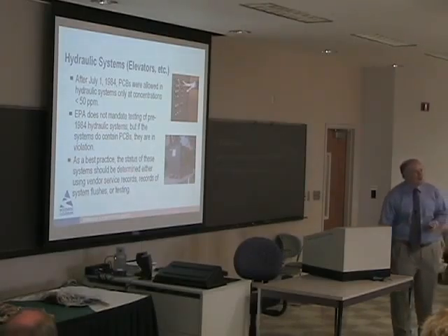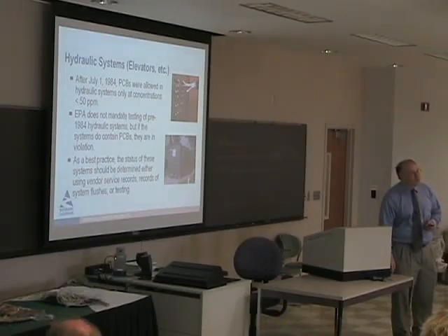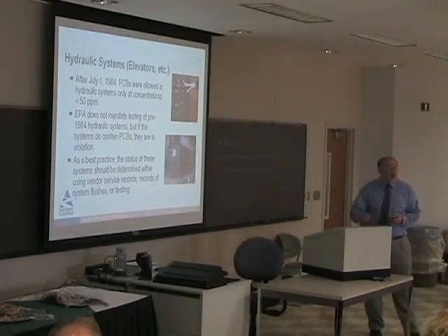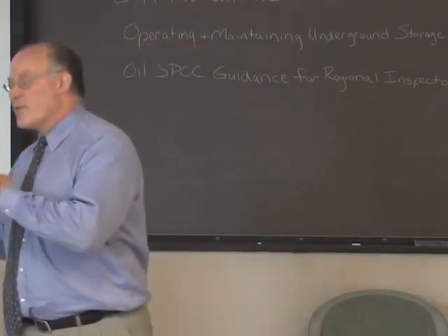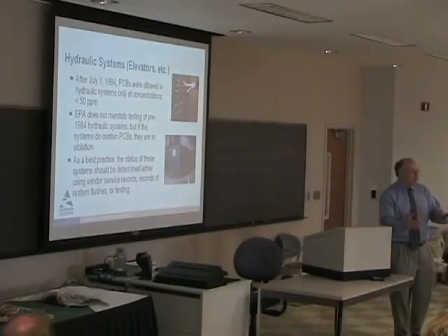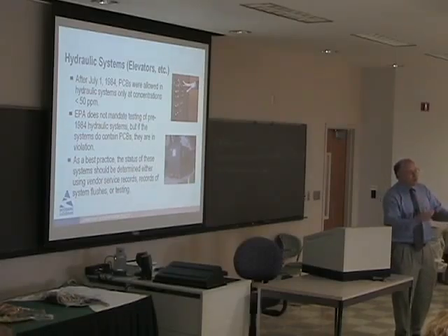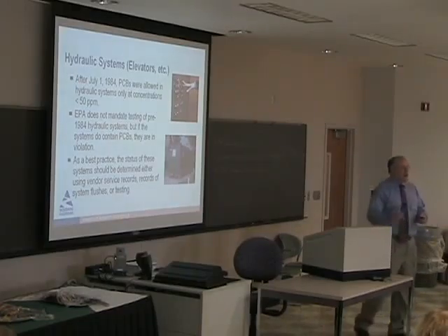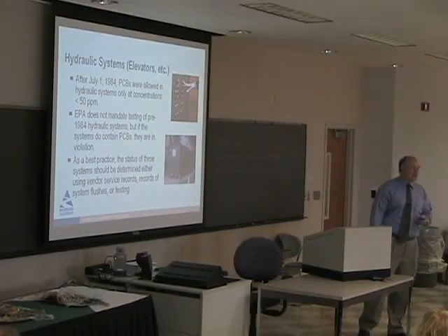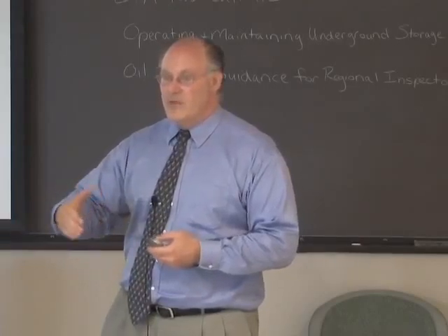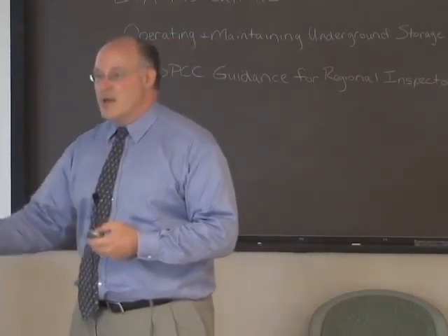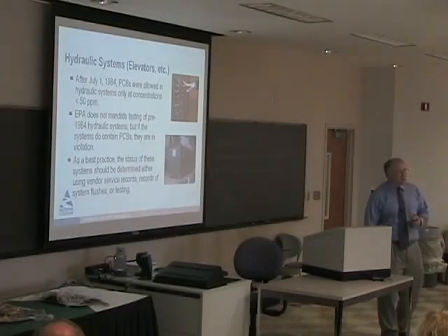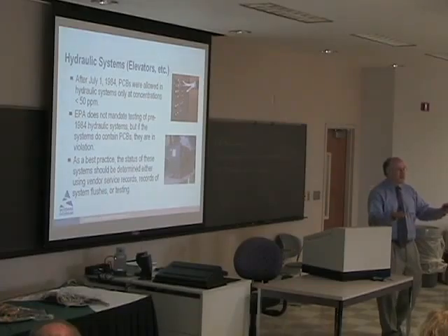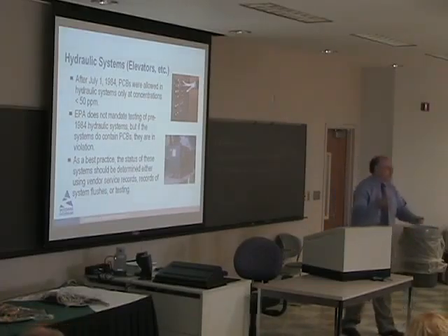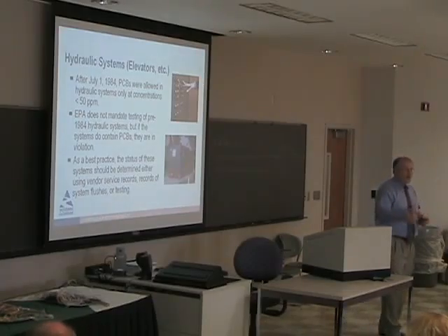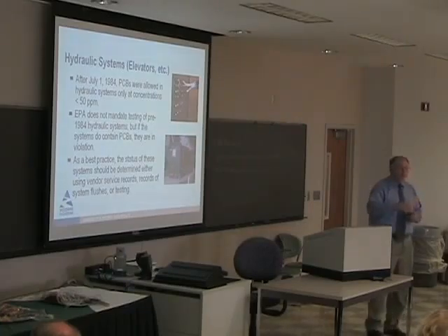Is there some characteristic that caused it to be allowed back in, that made stuff operate better? It's not that you would want to add it back in. It's that manufacturers of hydraulic oil, years ago, could put in as much PCB as they wanted because it was beneficial to some qualities desired in the oil. Starting in July 1984, you could only put in less than 50 parts per million as you manufactured it. From that point forward, you could not sell or use in the United States hydraulic oil that had 50 parts per million or more. It has certain beneficial qualities, just like asbestos does - that's why people originally used it. But at some point, the risk and danger of using it outweighed the benefits it provided to the equipment, so it was banned at 50 parts per million and greater.